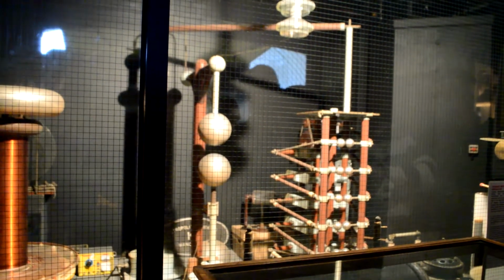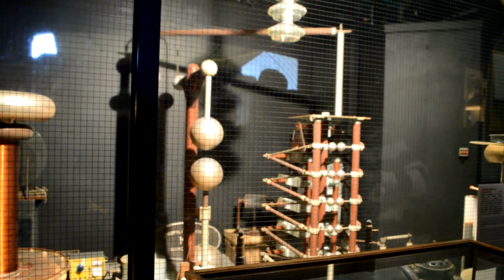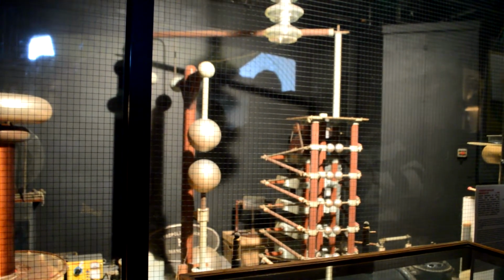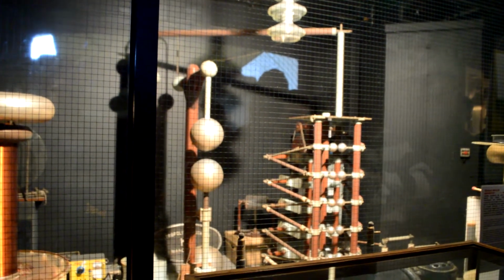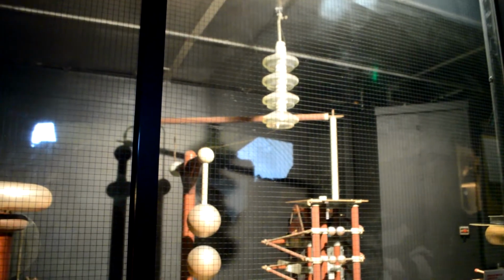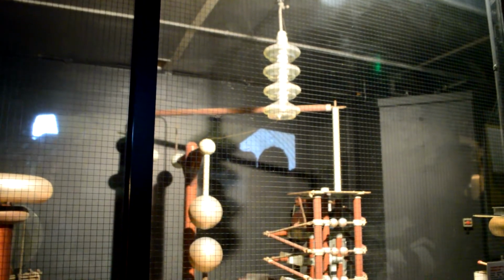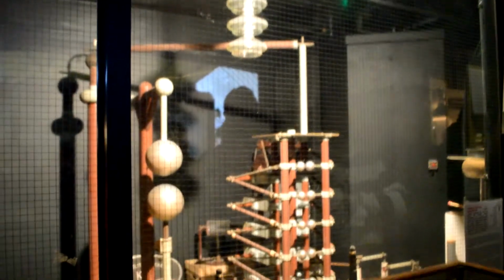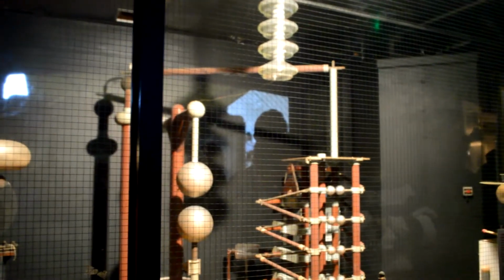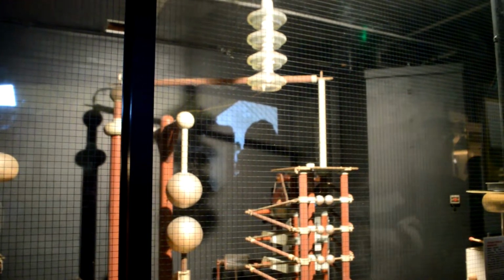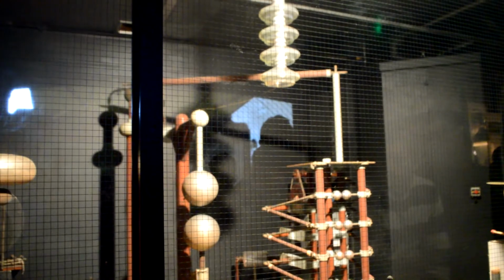Anyway, with a little bit of clever control and design, you can produce whatever peak voltage you choose of this test waveform. In our own simulation here, we've taken a string of glass disc insulators, such as you see on the National Grid pylons. You can see them hanging from the roof. We've made them faulty, but not completely faulty, by taping short lengths of copper wire across the upper surface of each glass dish. So there's no continuity between the lower one and the earth connection at the top, but it's like a series of spark gaps. And the electrical stress produced by the application of the impulse voltage will simulate the failure of those insulators under either a lightning strike or their own test.